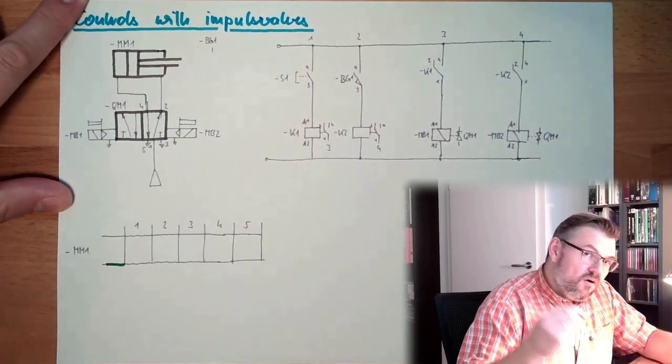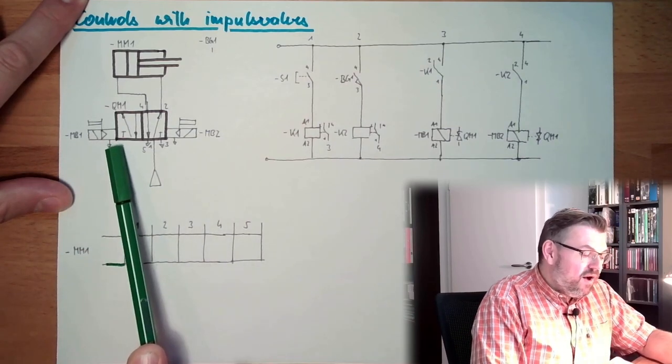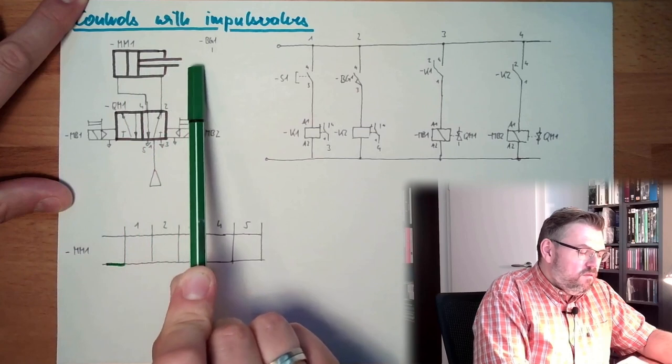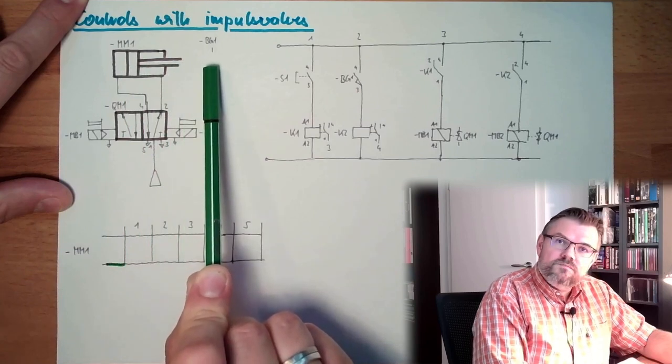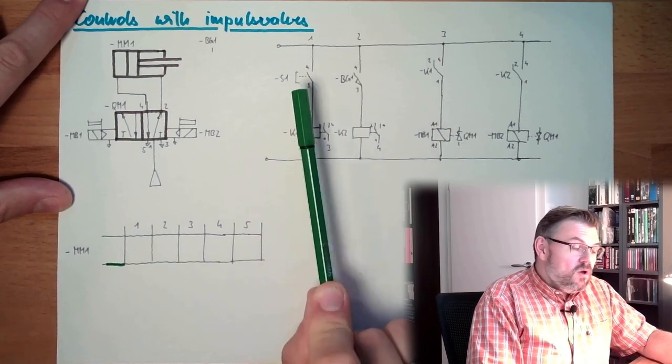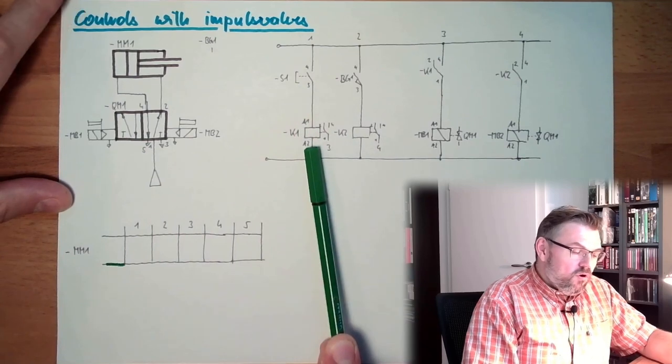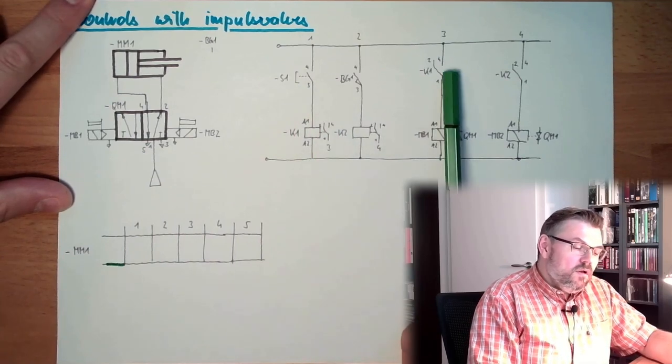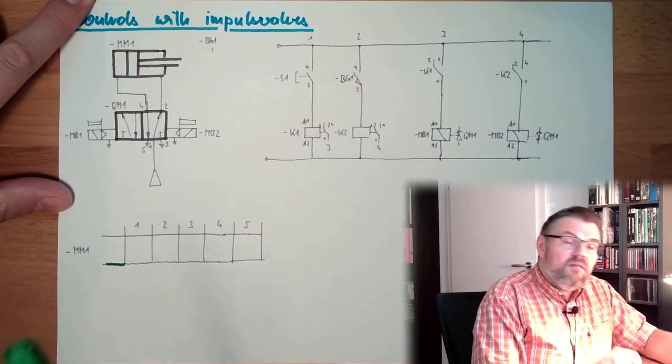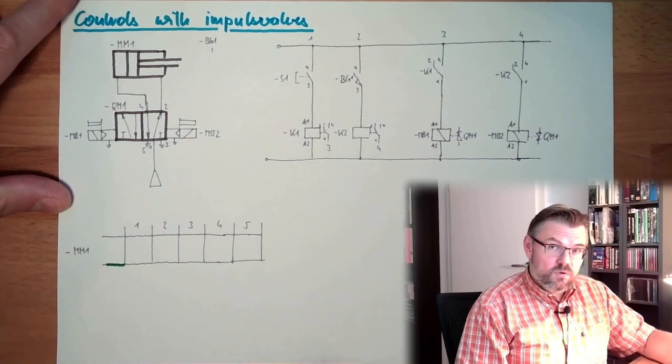MB1 is now energized. This will mean the valve is switched to the other direction. If the valve is switched to the other direction, this is moving outwards. During moving, we can already release S1 because it's an impulse valve. Even if you release S1, this will no longer be energized, this will fall. If this is falling, then this will also be not energized. However, the valve will stay that way, and we will finish the movement, regardless of how long S1 is pressed.